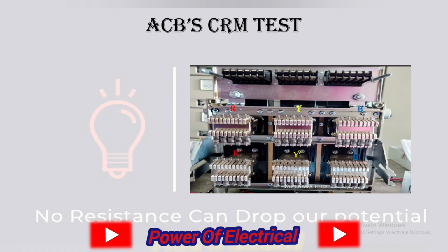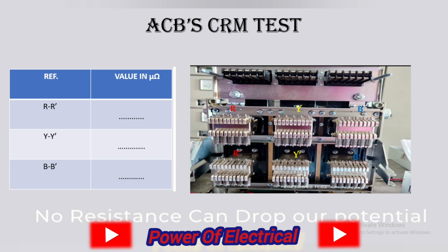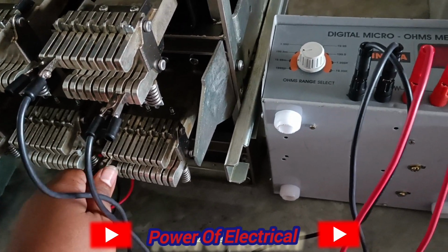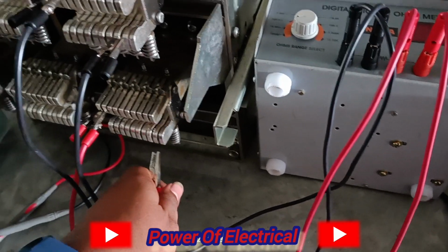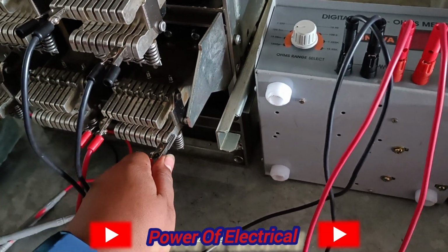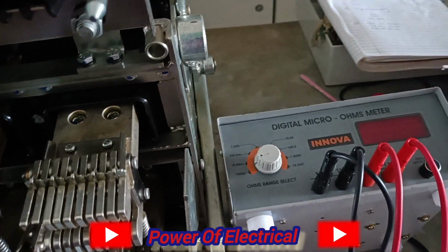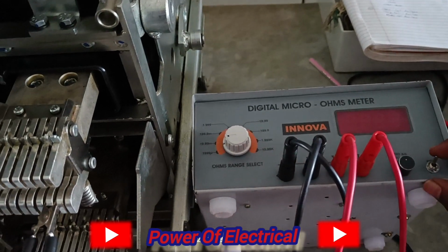Now the ACB CRM test means circuit breaker contact resistance test. For a circuit breaker, the CRM value should be in microohm. In the CRM test, we apply a DC current to the circuit breaker terminal when it is in the on condition, and we measure the voltage drop between the terminals. For a CRM test, we use a digital microohm meter, which has 4 probes, 2 mainly for the voltage and 2 for the current.